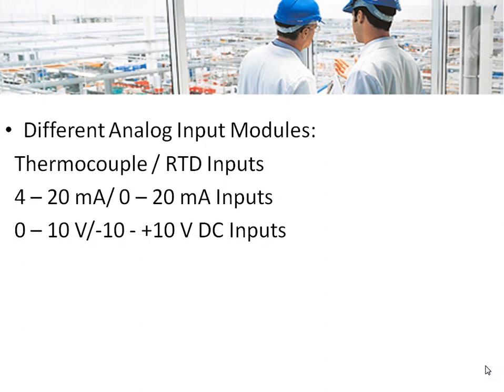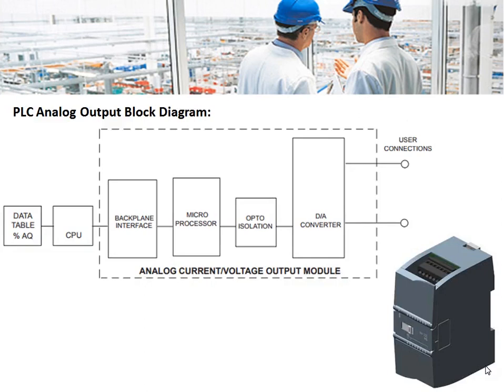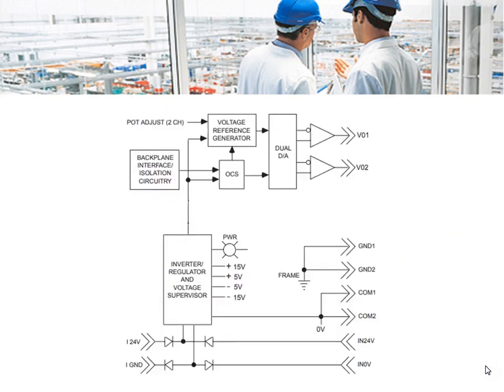The typical analog output block diagram is shown in the figure. The data from the CPU is interfaced through the backplane to a microprocessor or microcontroller, then through opto-isolation it is fed to a digital to analog converter. The commonly used DAC is the R2R type. In a two-channel analog output module, the signal from the CPU logic is fed through the backplane interface to the DAC and then to the field devices.